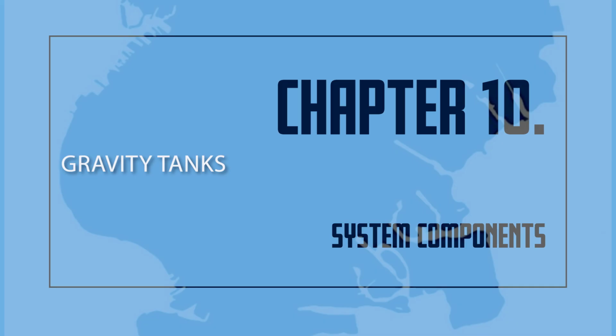Gravity tanks. Gravity tanks are used for water storage. They are made of wood, steel, or concrete. Gravity tanks are used as a primary or secondary water supply source for sprinkler systems. A gravity tank system delivers water from the tank through the sprinkler system without the use of pumping equipment. A gravity tank should be at least 25 feet above the highest line of sprinkler heads that it supplies.